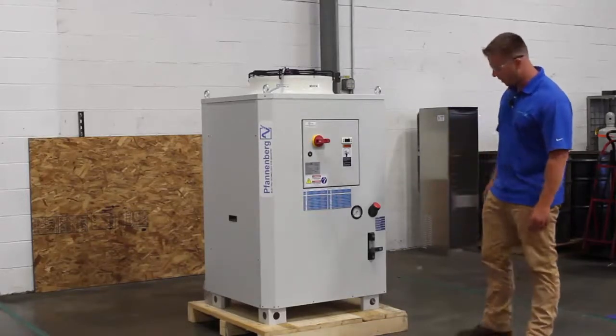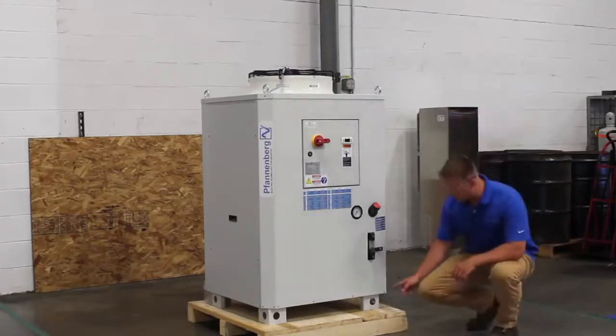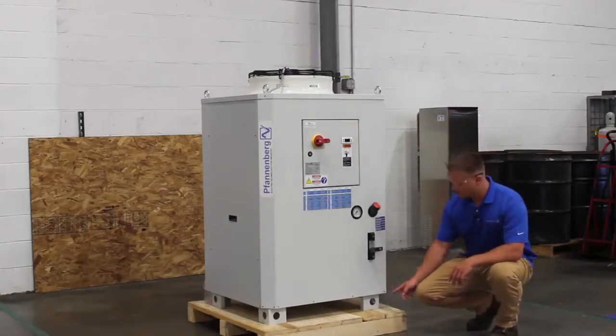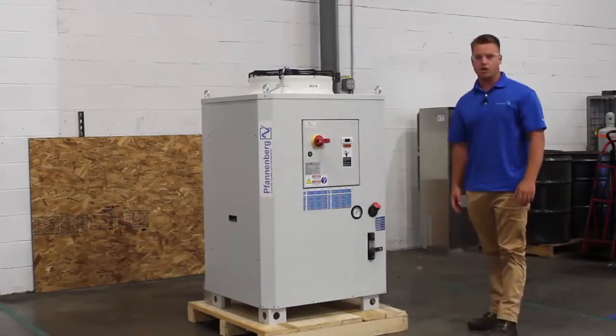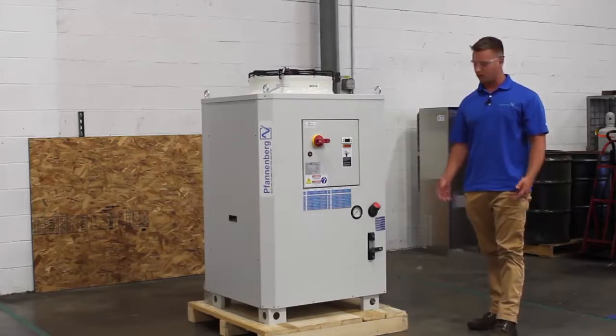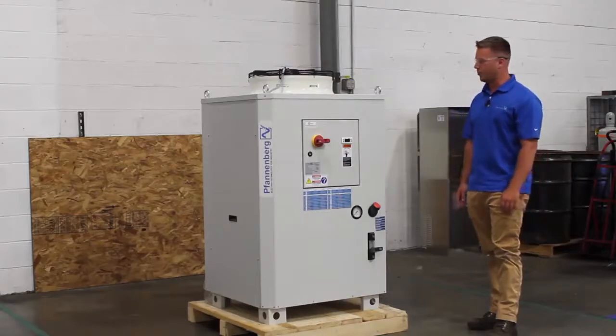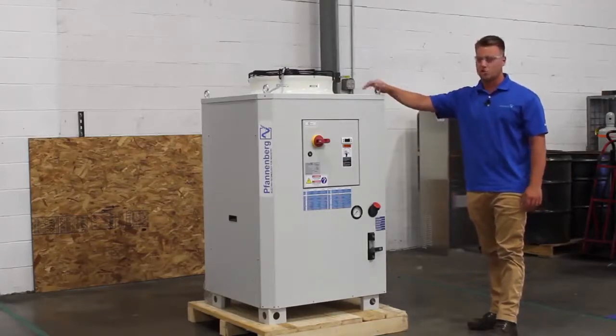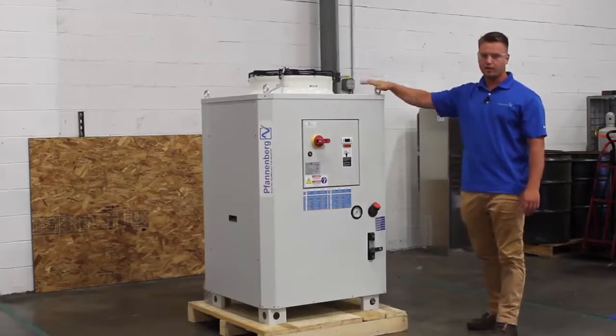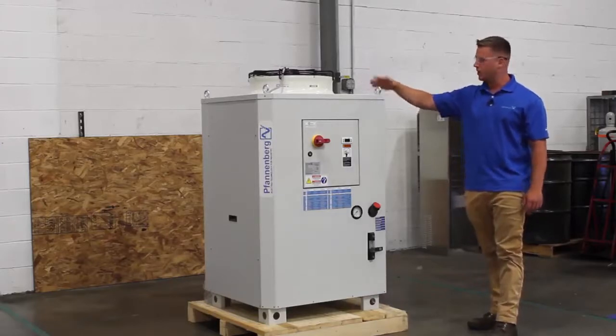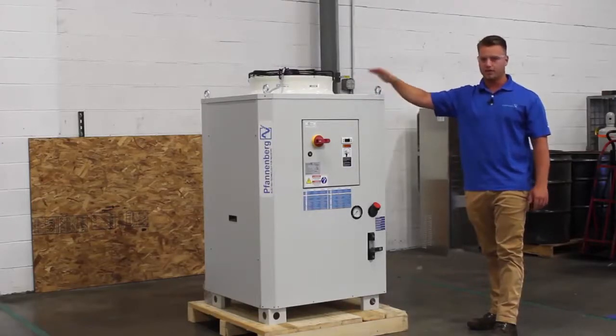I'm going to start off by pointing out that this chiller comes with a plinth here. So in case you're installing the chiller in a wet environment, wet or damp, the chiller is always elevated off the ground. The next thing I'm going to point out is the eye bolts on top of the chiller. This chiller is forklift ready, so as soon as it shows up to your site, you can raise the chiller off the pallet and set it right where you want it to be.